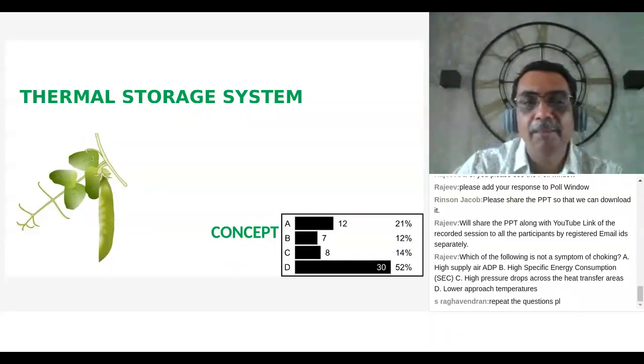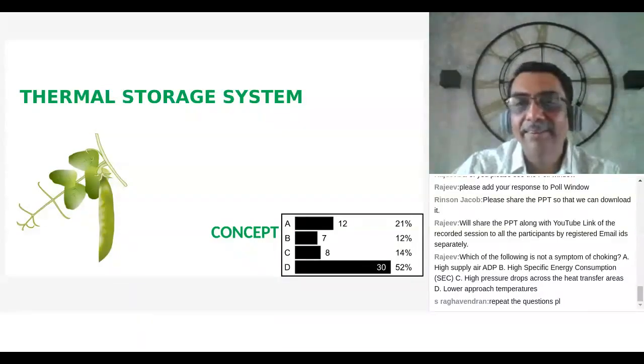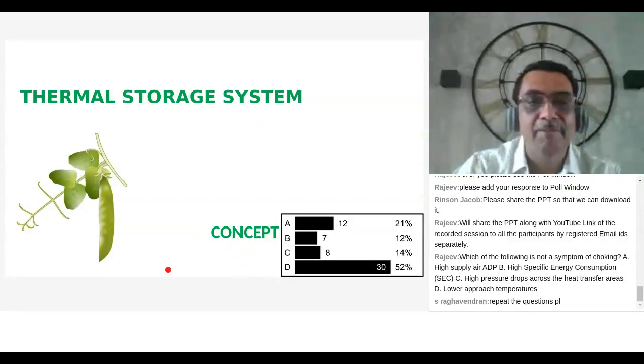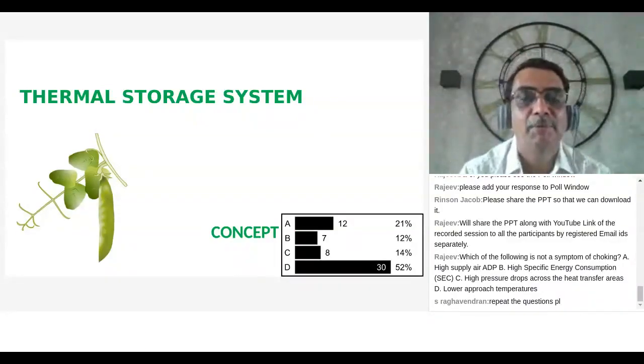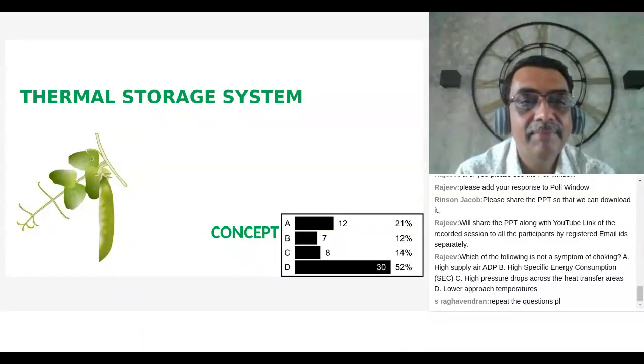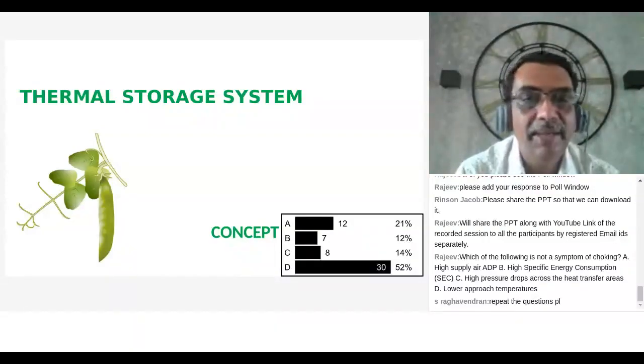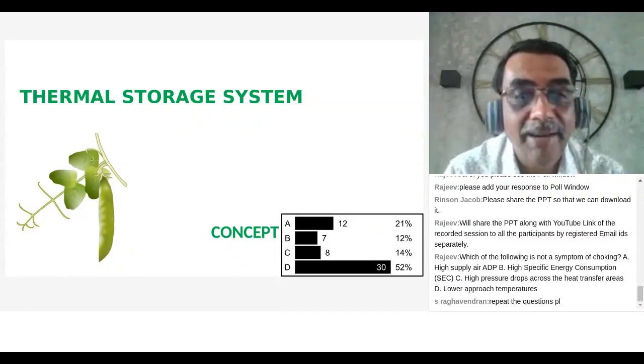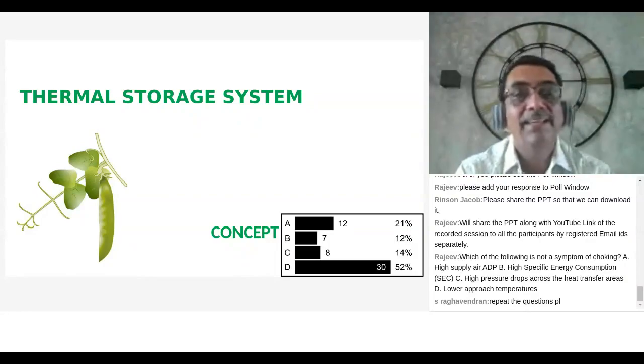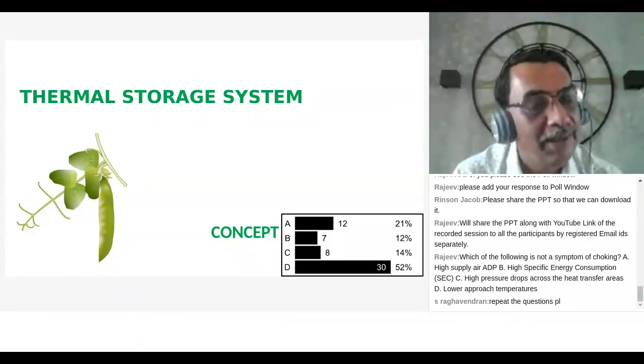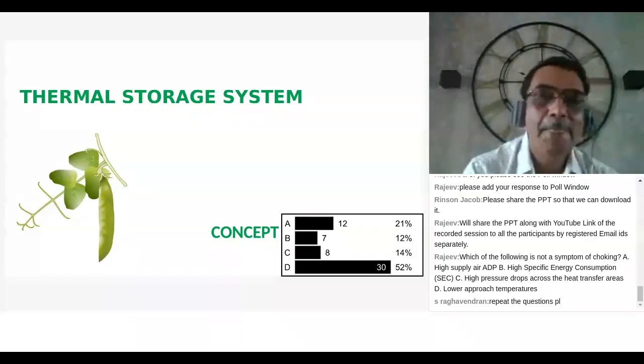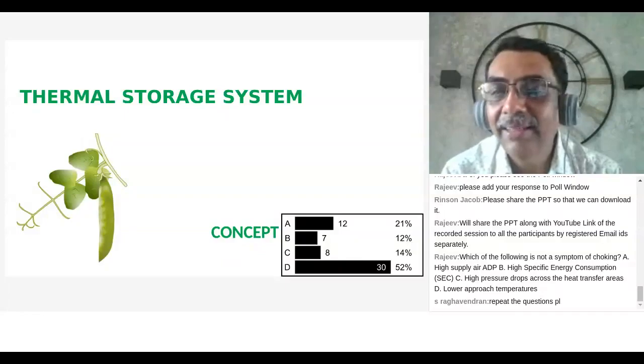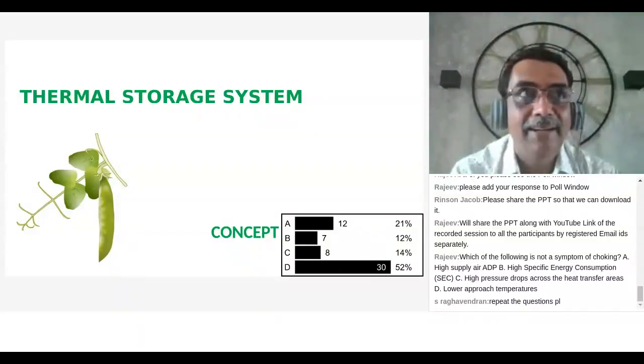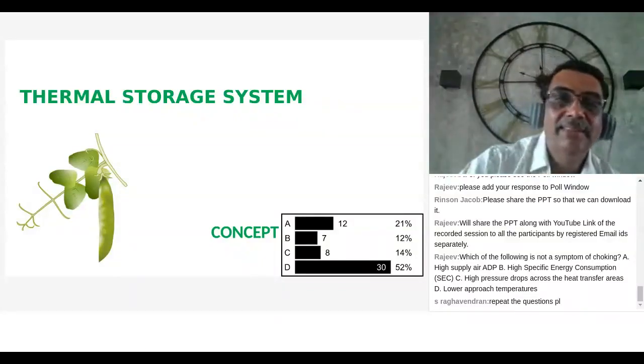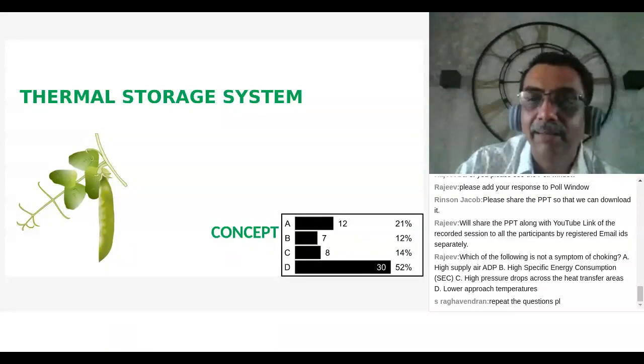So 53% of the people feel lower approach is not. Okay. 8 people, that is 14%, feel high pressure drop in the area is a symptom of choking. High supply air ADP, high specific energy consumption. And 53% of people are right. Lower approach temperature is not a symptom of choking. The approaches will become high if the system is choked. So good, at least 53% of people have got it absolutely correct. Thank you very much. For the people who missed it, that is 47%, I'm repeating.